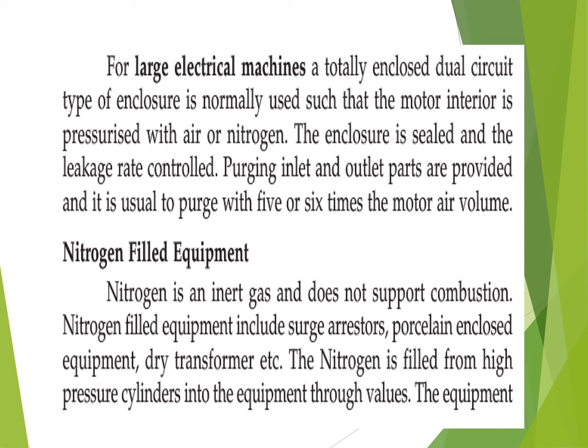For large electrical machines, a totally enclosed dual circuit type of enclosure is normally used, such that the motor interior is pressurized with air or nitrogen. Normally nitrogen filled inert gas equipment can be used. Nitrogen gas does not support combustion, so nitrogen filled gases can arrest the spark from coming out, and it may be used in dry transformers and all these areas.